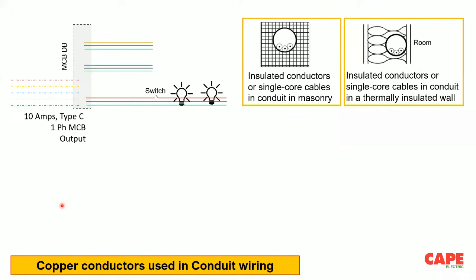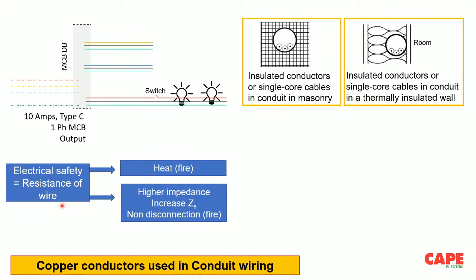Now, IS 732 has included filling factors, derating factors, voltage drop calculations, and several other factors with which you can select the appropriate size of the wire. For example, the wire manufacturer may claim that a 2.5 square mm wire can handle 20 amps, but practically in your building you have to use it only for 10 amperes. You cannot use it for 20 amperes because you are pulling it through a conduit with multiple wires in it, so you have to derate it. These derating factors are given in the standard. So, electrical safety with respect to wire, there are two things.